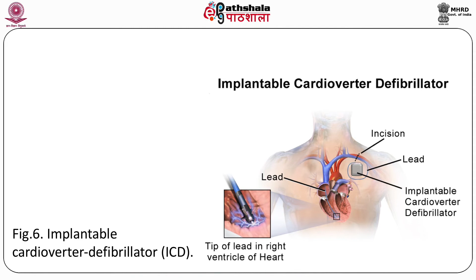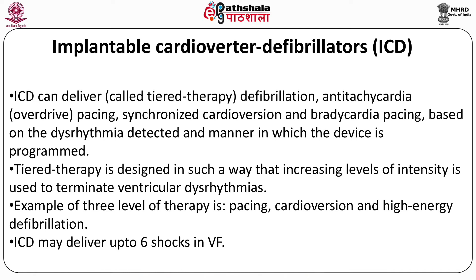An ICD can deliver tiered therapy, including defibrillation, antitachycardia pacing, overdrive pacing, synchronous cardioversion and bradycardia pacing, based on the dysrhythmia detected and the manner in which the device is programmed. Tiered therapy is designed so that increasing levels of intensity are used to terminate ventricular dysrhythmia. An example of three levels of therapy is pacing, cardioversion and high energy defibrillation. An ICD may deliver up to 6 shocks in ventricular fibrillation.